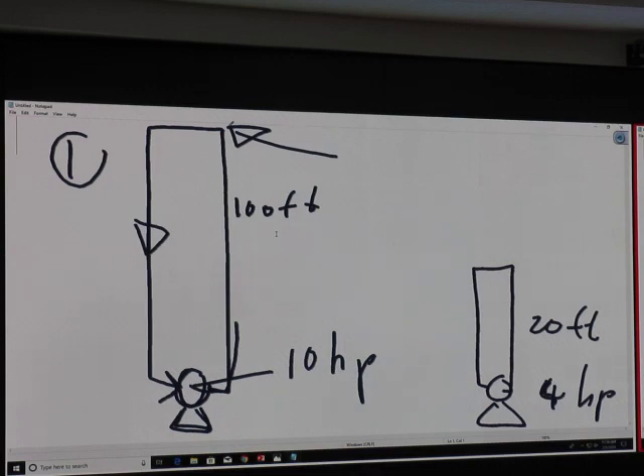So this means I need to have enough discharge pressure to bring the liquid up to that point first. So at least my pump needs to deliver 100 feet, so that it can pump on to that point. Then when it goes down, we get pressure. So this means when I look at the pump power, initially it requires more and more and more power. When we have flowing down, we require less power. Good. So the hydrostatic head term will cancel each other only if we flow down. When we flow down, it cannot create a suction so we gain pressure. If it doesn't flow down, or if it cannot reach that point, steady state calculation doesn't work.